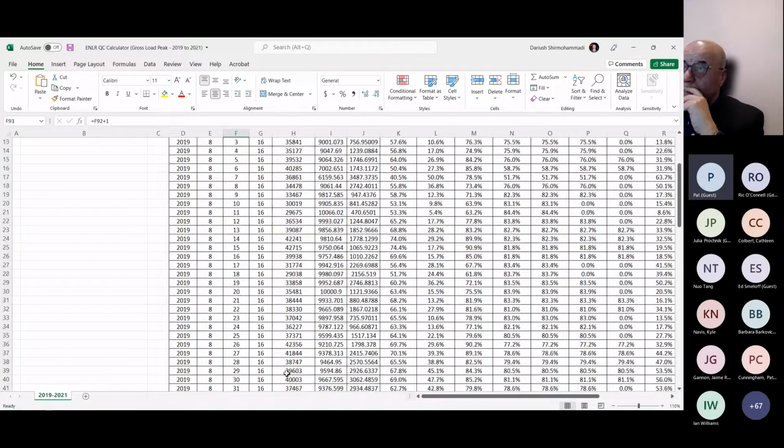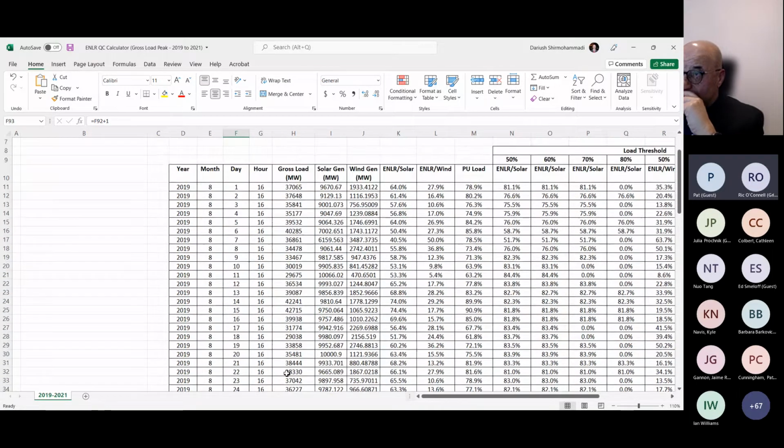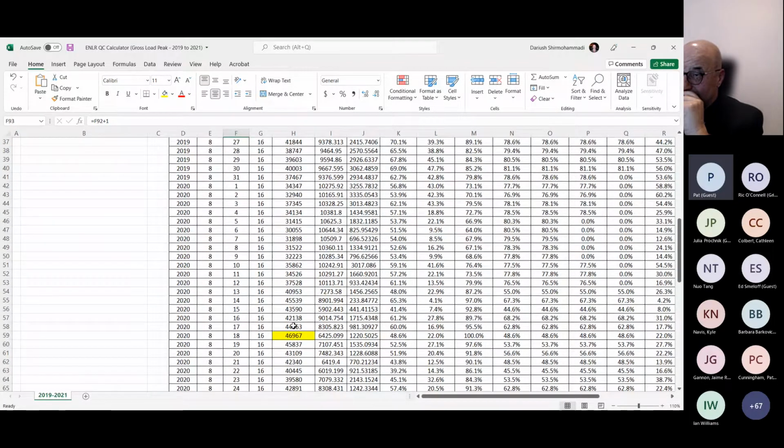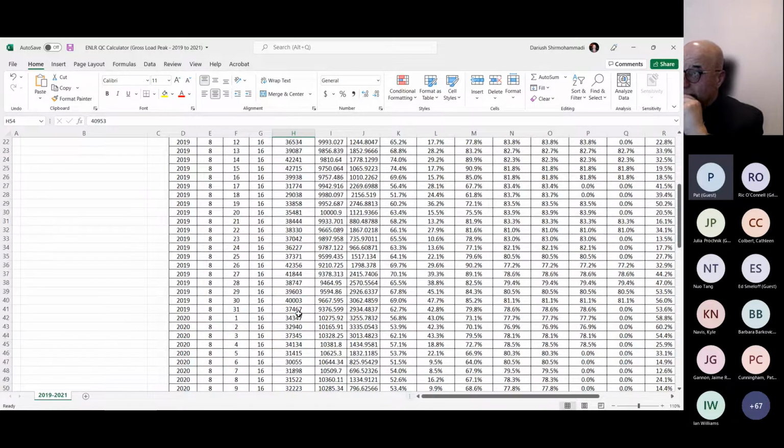So the load can vary quite a bit in that one hour. It's not like we have one load number only. The load changes quite a bit. And then our proposal is to focus on days where load is higher, and look at solar generation or wind generation only for days where the capacity or generation really counts, where the load is 44,000 megawatt or 39,000 megawatt, and then account for those. That's what the idea is.